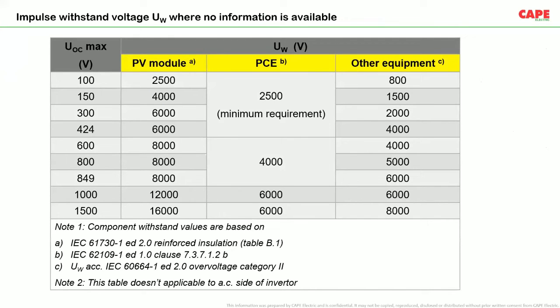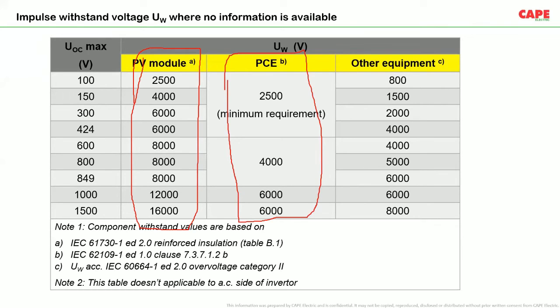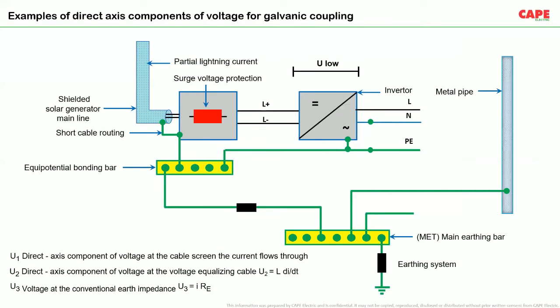Similarly, impulse voltage, safety against overvoltage: each part of the electrical installation of the PV must withstand a certain impulse withstand voltage. Of course, in the PV module, these impulse voltages are ensured by the PV module manufacturer, depending upon its voltage. But at the PCE, you have to be very careful. If you are buying a PCE which is not tested as per the standard, you have to ensure that the PCE is rated or tested for this particular parameter. What I have seen is that most of the inverters sold or used in India sometimes do not have this parameter tested. The danger is it can fail anytime and it can catch fire. So you have to use an inverter which is tested for all these parameters.